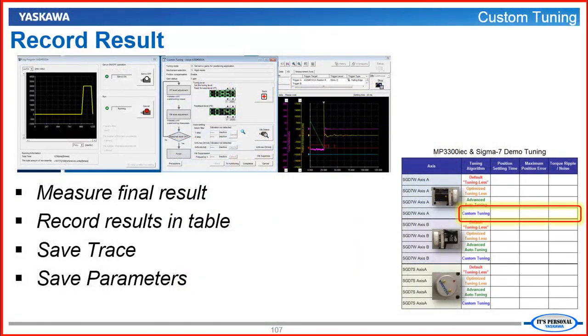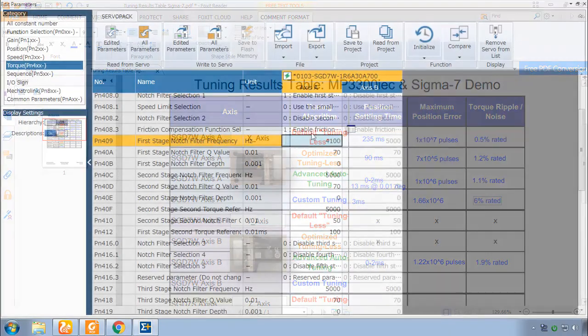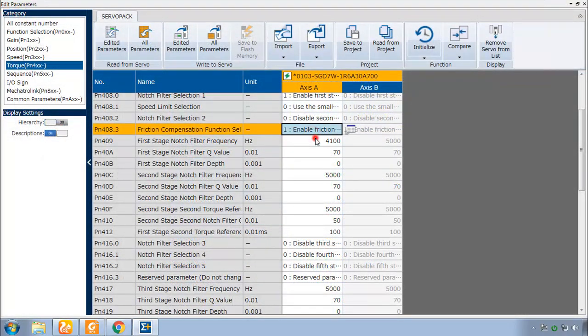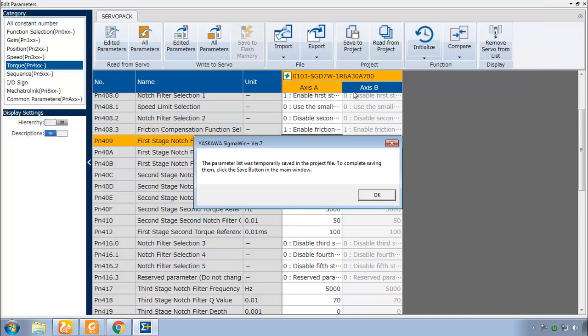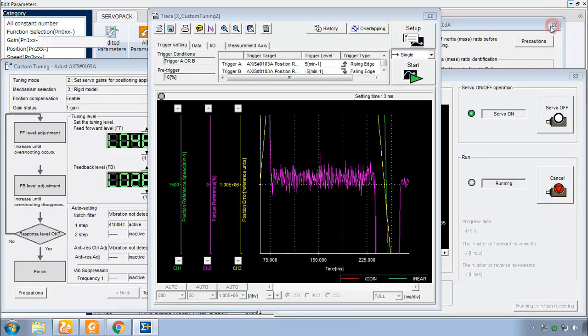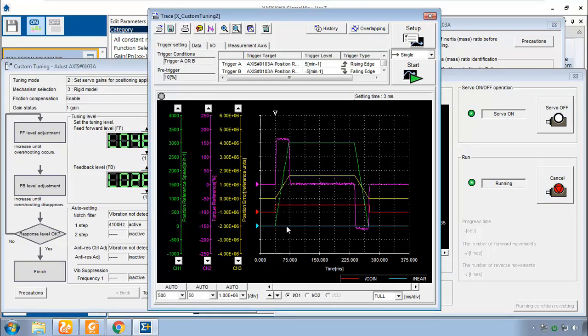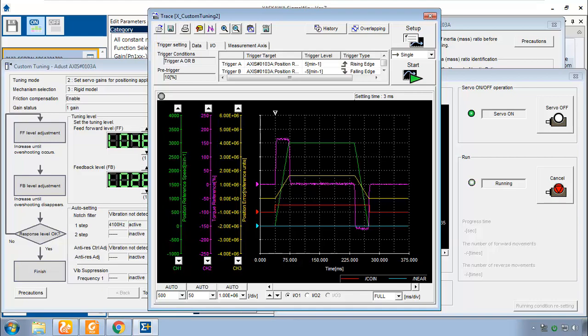However, I do know that this will sacrifice some position error during the move, but I'm not too concerned about the position error during the move. I was just trying to get the lowest possible settling time. I do have the notch filter at 4100 Hertz which you see here, and I set that using the online parameter window like I pointed out before. I should save this graph, call it X custom tuning, and I should take another one of the whole move. Let's do that, positioning from the start again with high precision. OK. One more. And here my settling time is still given as 3 milliseconds. I should measure this position error a little bit more accurately here. The difference is 1.6 times 10 to the 6. Let's look at how bad the torque signal got. It looks like we're talking about 6%. It's a pretty high torque ripple. So you see there's always a trade-off if you want this low settling time of 3 milliseconds, you won't also have the quietest motor in the lowest torque ripple. We're truly optimizing for the point-to-point move. I should save this trace to custom tuning number 2. OK.